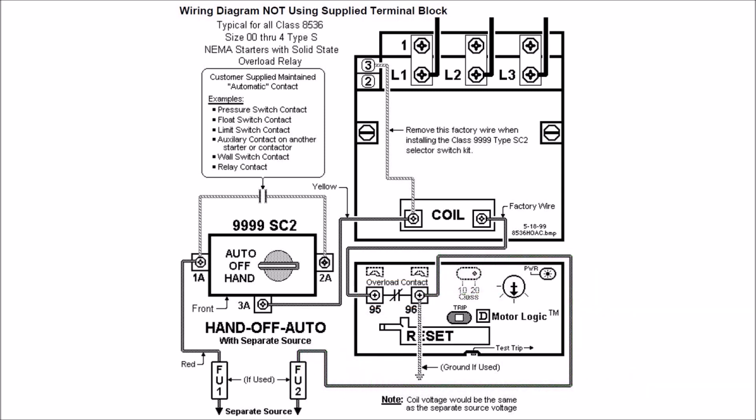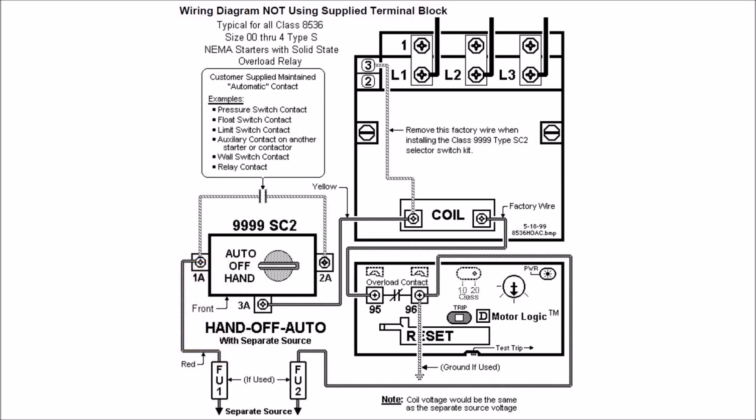For your handoff auto side, you'll have for separate control, usually your hot leg, you'll have that wired to your 1A of your handoff auto. And then you'll connect 3A to the left-hand side of your coil.